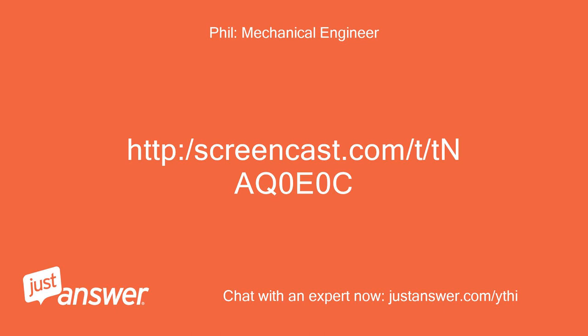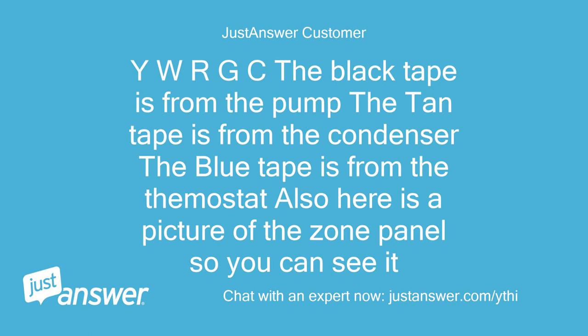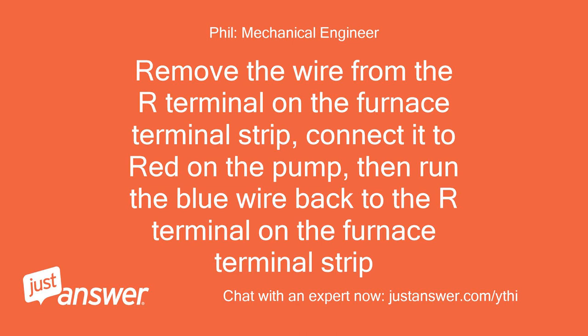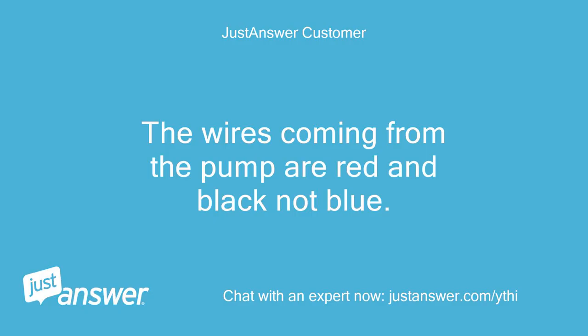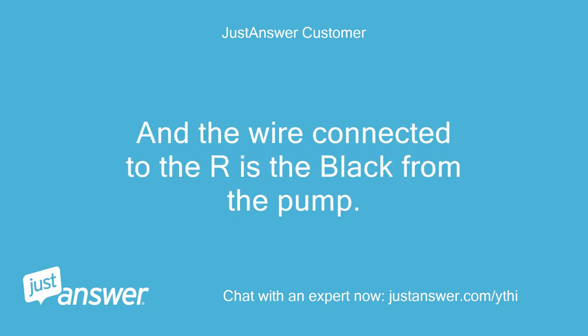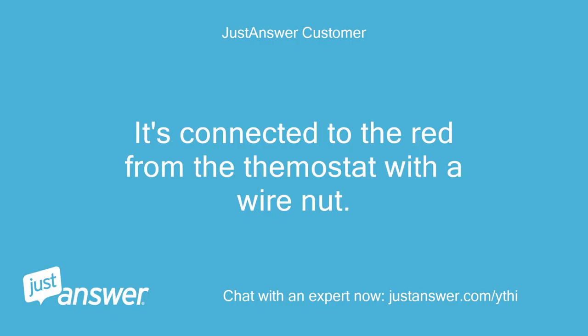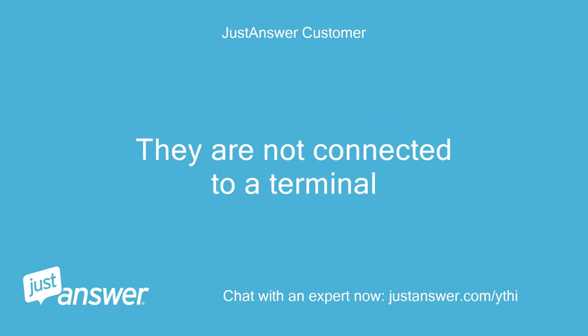HTTP screencast.com/t/tNAQ0E0C — Y, W, R, G, C. The black tape is from the pump, the tan tape is from the condenser, the blue tape is from the thermostat. Also here is a picture of the zone panel. The red and blue from the pump are for a built-in overflow prevention switch; it is used to shut the entire system down if the pump quits working. Remove the wire from the R terminal on the furnace terminal strip, connect it to red on the pump, then run the blue wire back to the R terminal on the furnace terminal strip. The wires coming from the pump are red and black, not blue, and the wire connected to R is the black from the pump. That's okay — where is the red from the pump connected? It's connected to the red from the thermostat with a wire nut — they are not connected to a terminal. That should work.